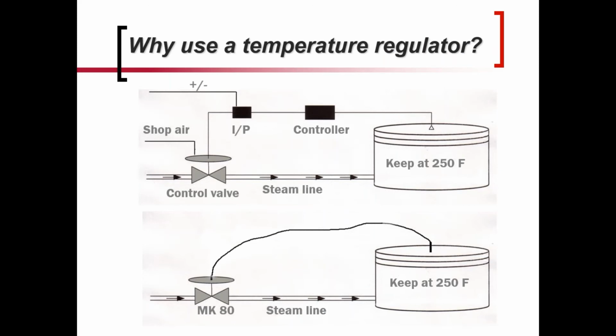So why would someone use a temperature regulator? There's a lot of different ways available to people and maintenance folks, engineers, to maintain, like in this case, tank temperature control. So in this example, we've got two different means of doing this. We want to keep a tank, heat exchanger, whatever, at 250 degrees F. Pretty straightforward. And so the top part shows what we see quite a lot of, a control loop in order to make this happen. So you've got an actual control valve, which is being operated with a 4 to 20 through an I to P, and you've got some type of controller, and there's going to be a temperature sensor in this tank that sends its signal back to this controller, which then tells the I to P, and the controller will send the signal to stroke the valves to either increase the amount of steam, decrease the amount of steam based on the temperature sensor.